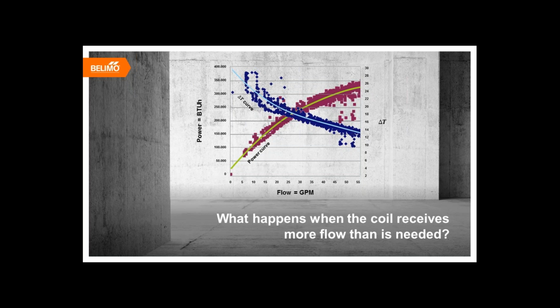What happens when our coil receives more flow than is needed? As the flow increases beyond 55 gallons per minute, as you can see on the bottom of the graph, the power curve begins to flatten. Then power output actually diminishes as the flow continues to rise. The coil is entering a point or an area that we call power saturation.